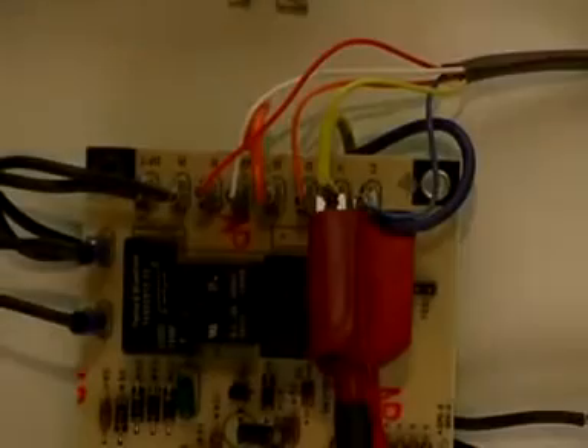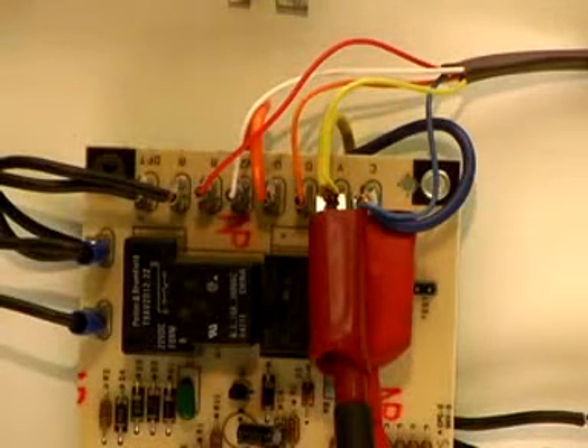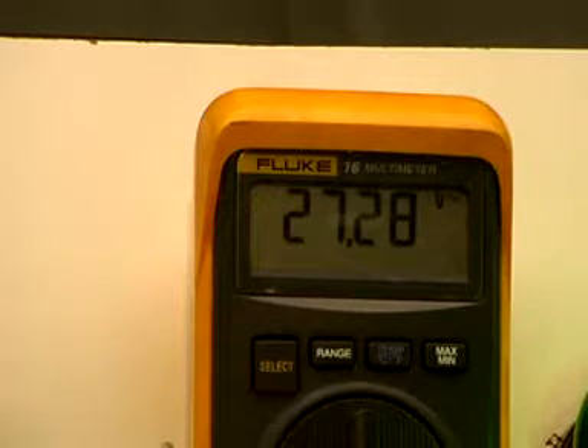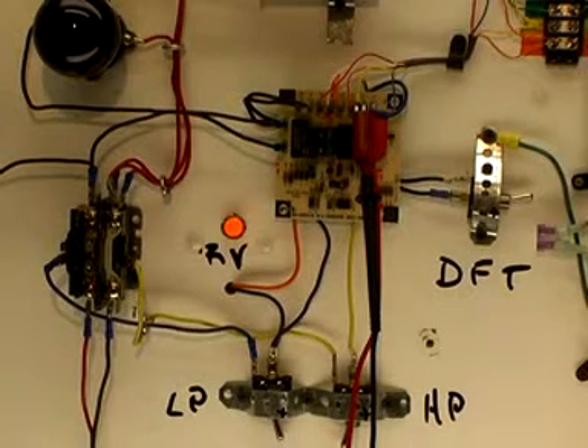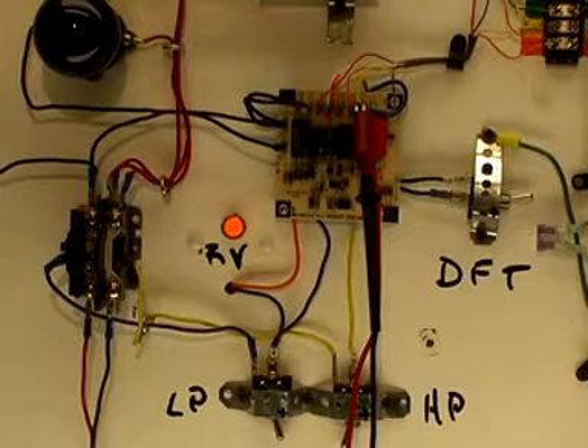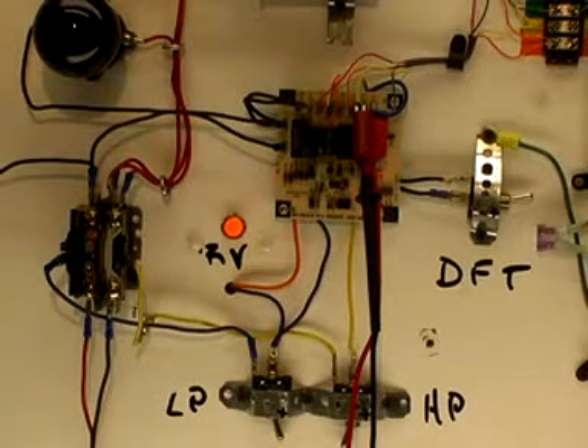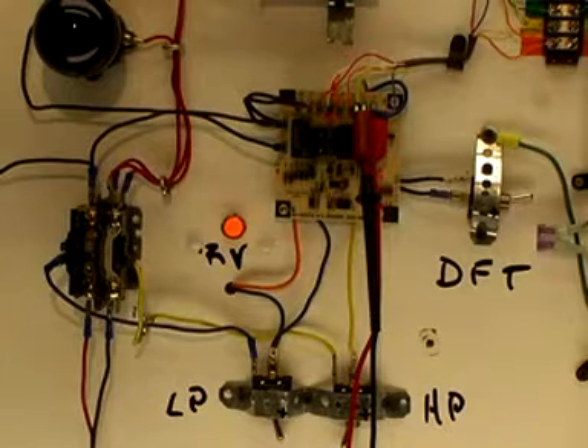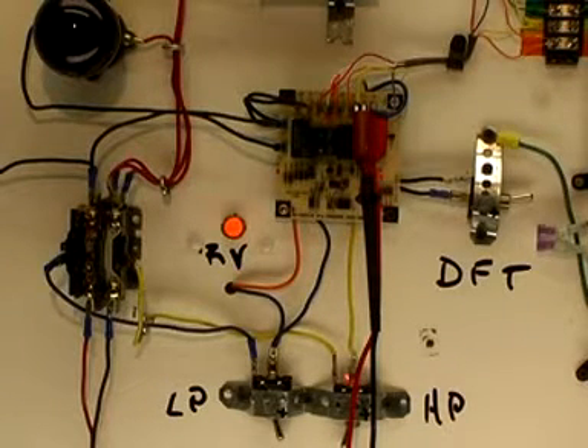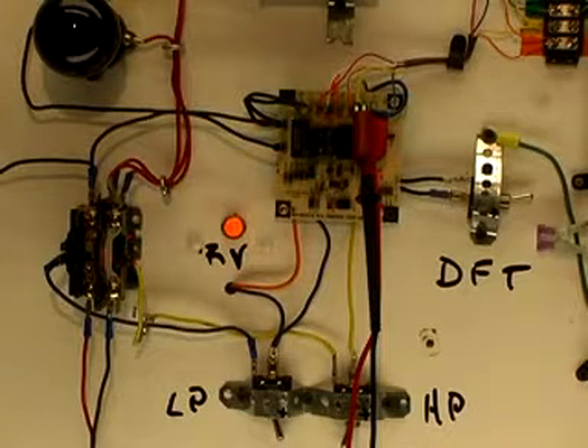At this point, we're actually measuring the voltage coming in from the thermostat, and we can see that we're getting 27 volts. So we know the problem is somewhere between the defrost board and the contactor coil. Either by looking at the wiring schematic or just visually tracing the wire, maybe using your hand and your eyes, you can quickly see that the yellow wire leaves the defrost control board, goes down to a pressure switch, comes out of the pressure switch, and then goes over to the contactor coil.